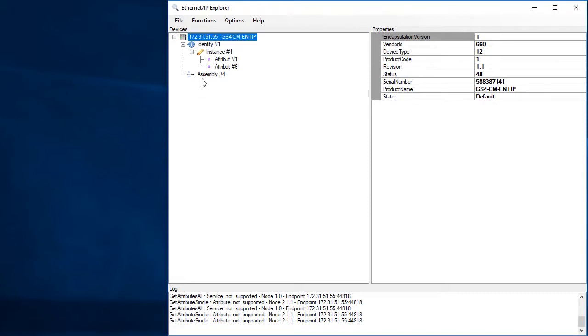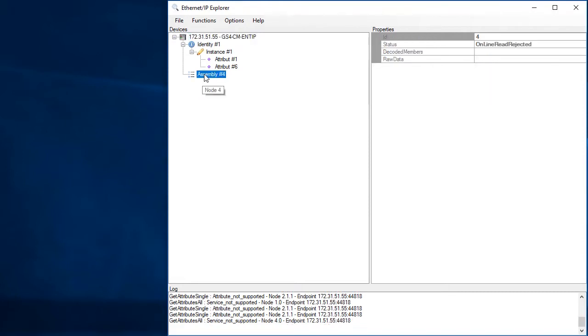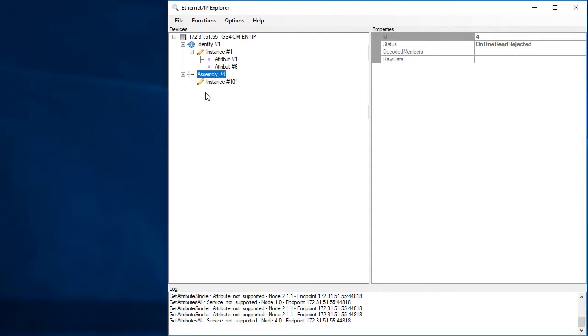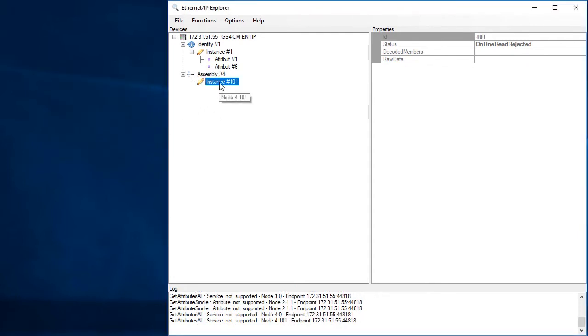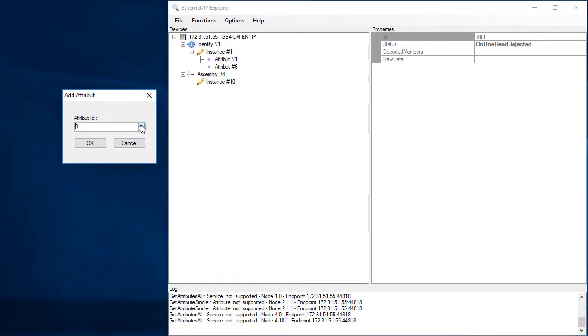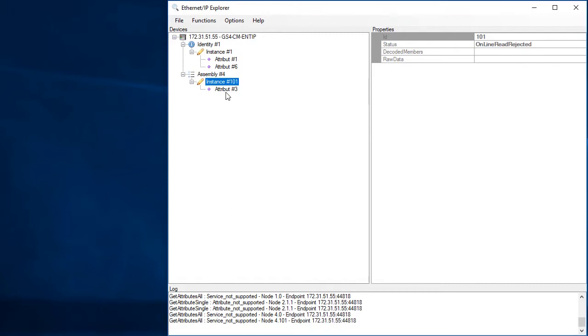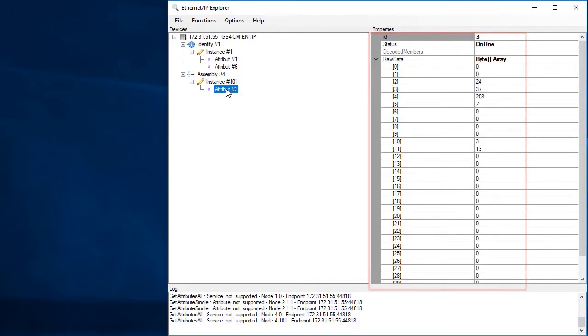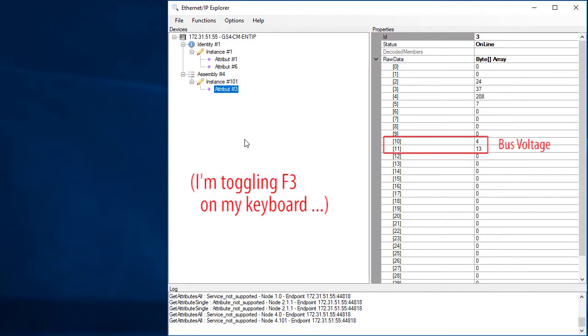Left click on the class, then right click to add an instance. I know the input buffer is instance 101. Which attribute do we want? Turns out there is only one input buffer and its attribute number is 3. If I left click on that attribute, the Ethernet IP Explorer app goes out and reads the entire buffer and shows it to me. I know this is the bus voltage and if I hit F3 to refresh the screen, I can see the bus voltage fluctuate.